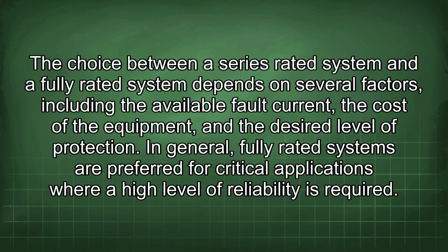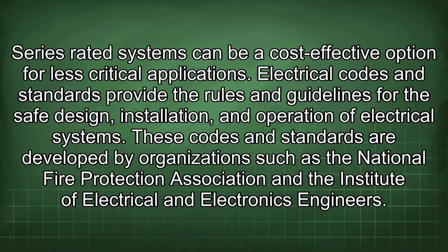The choice between a series rated system and a fully rated system depends on several factors, including the available fault current, the cost of the equipment, and the desired level of protection. In general, fully rated systems are preferred for critical applications where a high level of reliability is required. Series rated systems can be a cost-effective option for less critical applications.